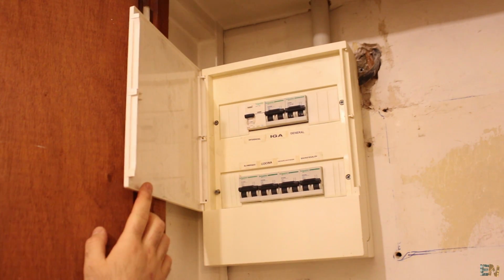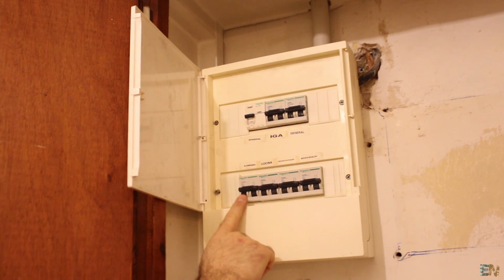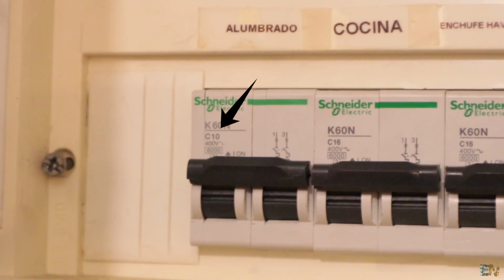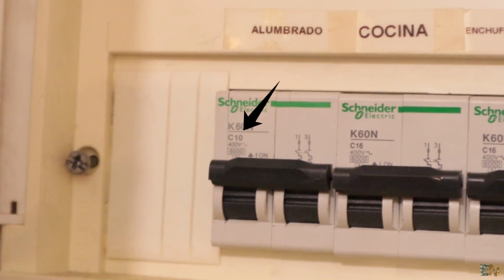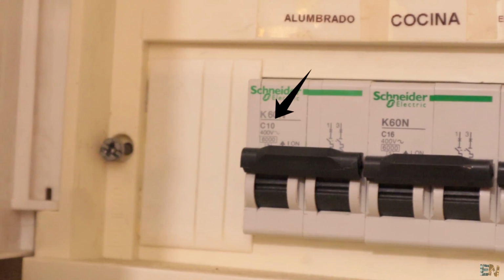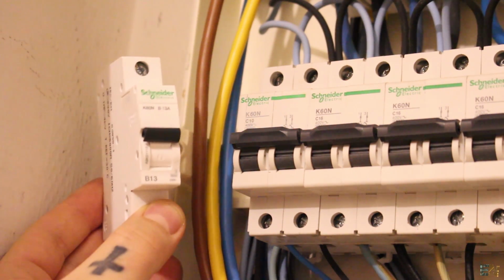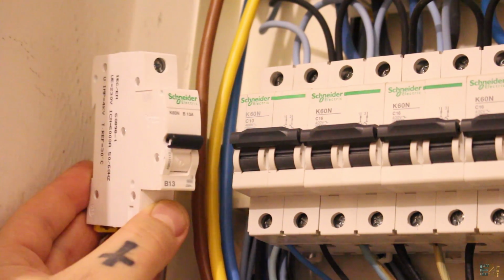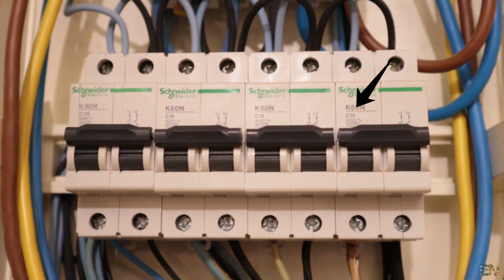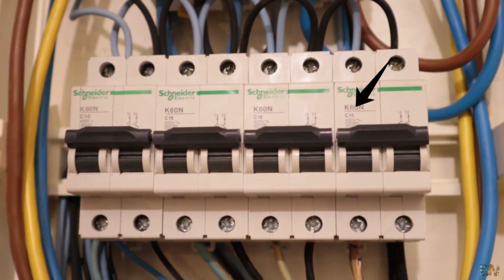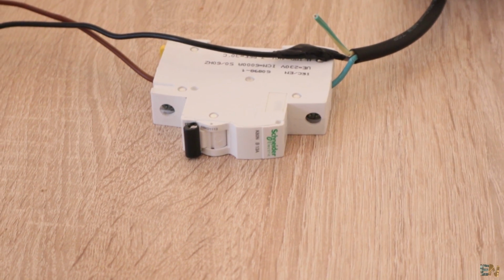Now I can't do this in my workshop, because the breaker from my home electrical panel is rated to 10 amps, which is lower than the one that we are testing. So for sure my home breaker will jump before this one. But for that I go to my living room, because here I have a breaker rated to 16 amps, and the one that we are testing is 13 amps, so this should jump first.